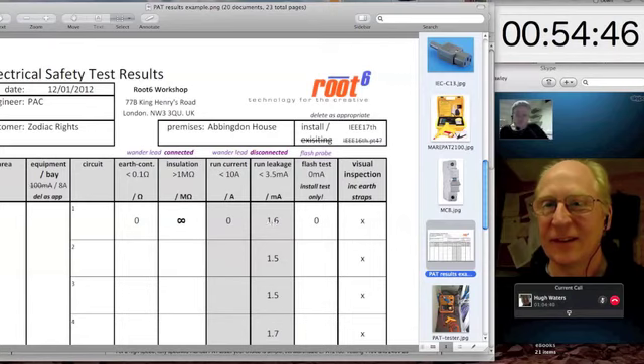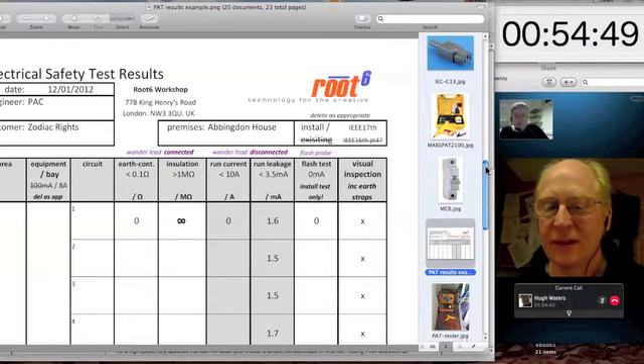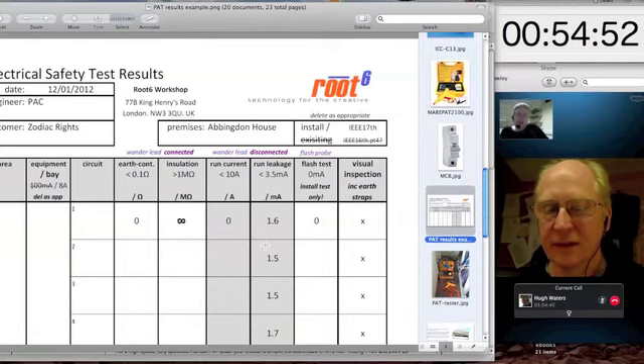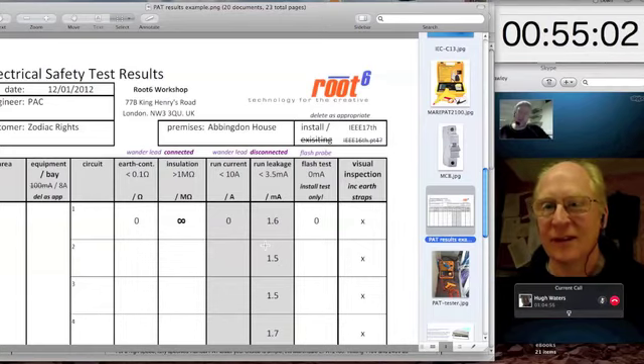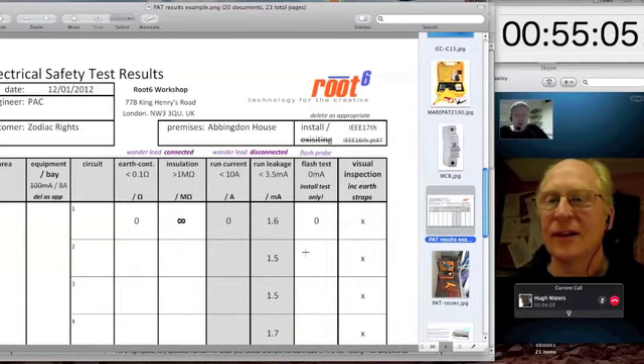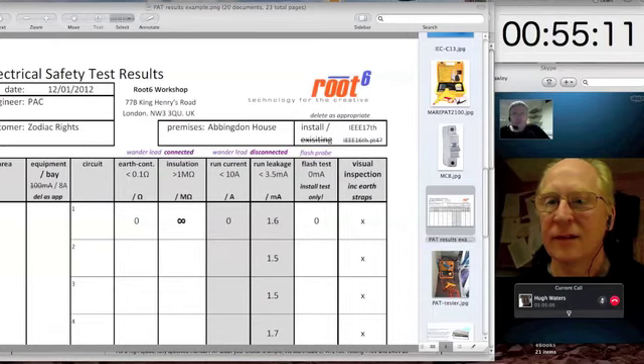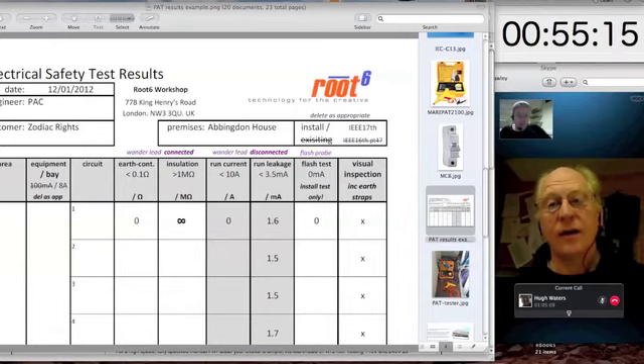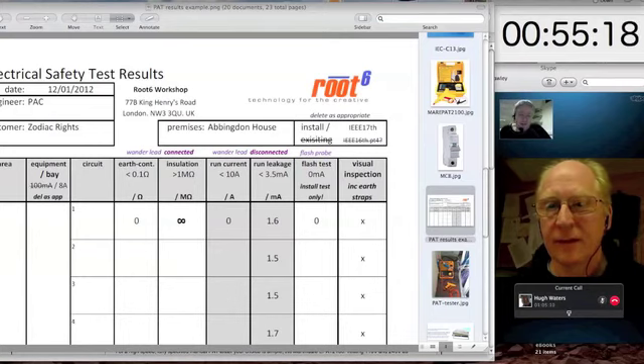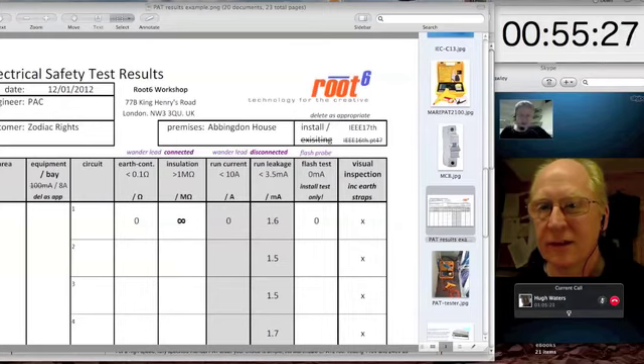of the power distribution strip. The next thing we do, very important, this is probably the most important thing from a safety point of view, is the run leakage test, and that measures the amount of leakage between the live and the earth, and the neutral and the earth, and that must be below 3.5 milliamps. And the reason for that is that if it isn't, then residual current detectors can't work. If equipment is starting to introduce leakage current, then that nice RCD that's sitting in the power distribution board on the wall of the machine room is ineffective. It can't work if it's having to deal with leakage current caused by the equipment, not caused by a fault condition, but caused by the equipment.